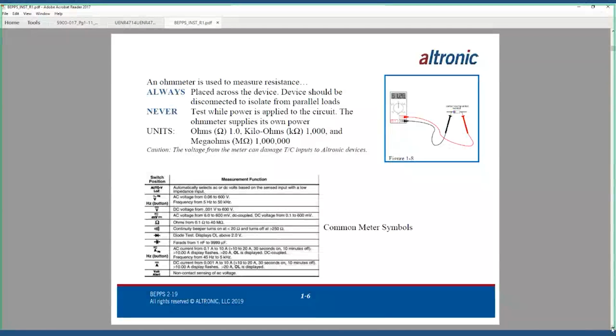An ohm meter is used to measure resistance. Always place across the device. The device should be disconnected to isolate it from parallel loads. So if I have a complicated circuit board or a complicated wiring harness or wiring circuit in a control panel on a unit out in the field, if I'm wanting to measure the resistance of it, I can't just start measuring resistance. I have to isolate what I'm measuring resistance on. So I may have to go undo connections at the far end of the skid or at the other end of the panel, but it has to be isolated or you're going to get a false reading. If you don't isolate it, you're wasting your time. Never test while power is on the circuit. The ohm meter supplies its own power.